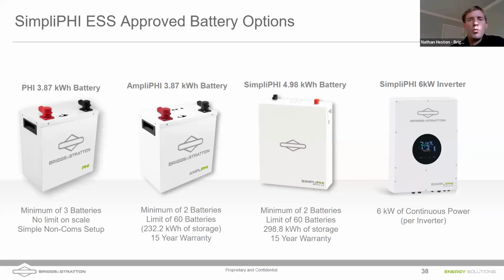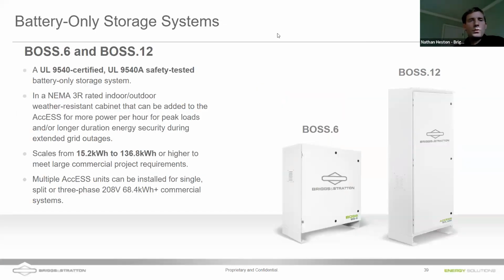And that SimpliPHI battery is a wall hung battery. We have enclosures that give us some options for the PHI and the AmpliPHI battery if you do want to install them outdoors. This is our Boss 6 and Boss 12 cabinets. These are UL 9540 certified, UL 9540A safety tested, and NEMA 3R rated. If you want to install them outdoors, you need to have these little rain hoods on the temperature regulated fan in that cabinet. But these are rated for outdoor install, so you can install the PHI or the AmpliPHI battery outside, but you would just want to do it in one of these enclosures.